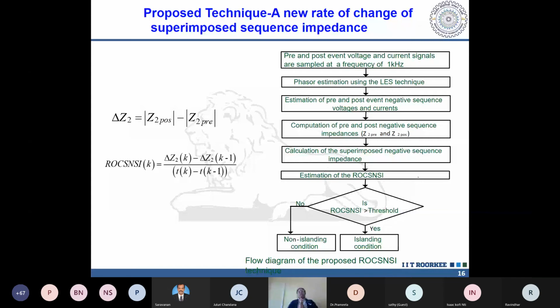So we grabbed a new technique known as superimposed sequence component based technique. What is the superimposed negative sequence? When a fault occurs, you have negative sequence component present, along with positive sequence and zero sequence. Why did we target negative sequence here? Two things: the negative sequence based technique is not affected by load change.